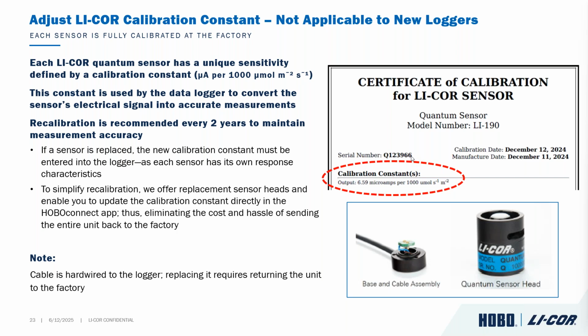This is, let's say you have your device and you've used it for a couple of years, right? Again, as I mentioned earlier, each sensor is unique. It has a sensitivity that's defined by this calibration constant. So when we manufacture this product, we take that calibration constant and we burn it, for lack of a better word, into the data logger. And that's what makes sure that we convert that electrical signal accurately so we can make accurate measurement.